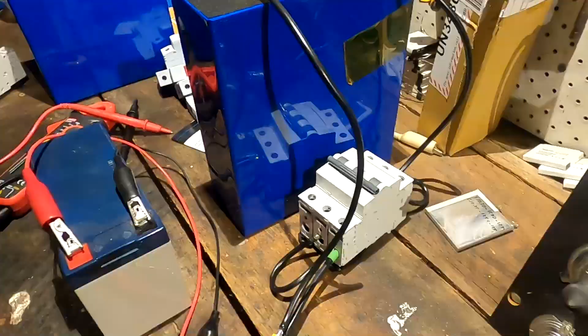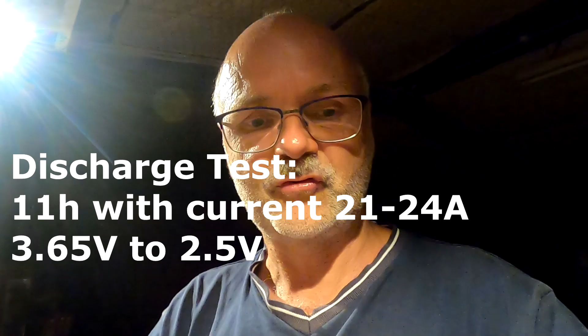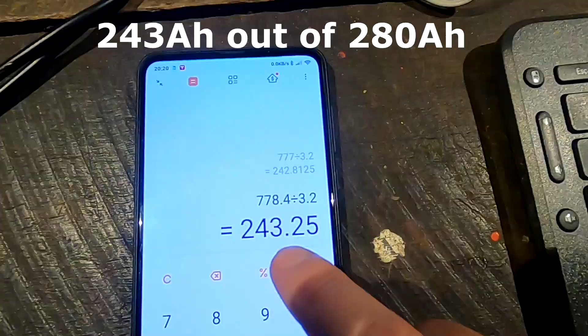So we have pulled only 24 amps out of the battery, and it took exactly 11 hours to discharge the battery from fully charged 3.65 volts to now 2.5 volts, and this is the cutoff voltage as per the specifications. This results in 243 ampere hours and not 280 ampere hours as advertised and sold.